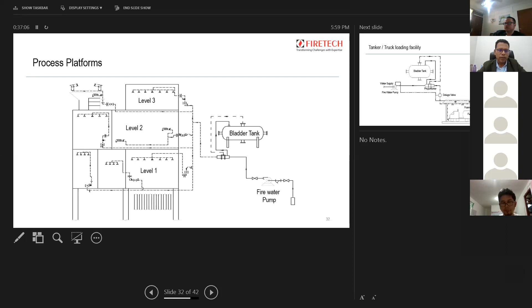Now, the tanker and truck loading facility. Here, these foam systems are provided for tanker loading bays, where trucks are used to transfer, load or unload hydrocarbons or polar solvents. It consists of a detection system with detectors. These detectors detect the fire and send a signal to the alarm panel, and the alarm panel actuates the deluge valve. Due to the actuation of the deluge valve, the foam solution is spread from the top as well as from the side nozzles in a truck loading facility.